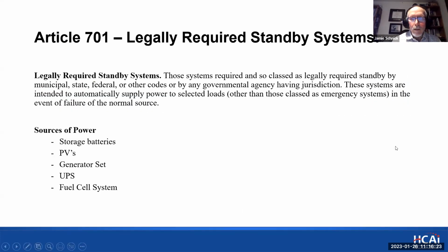Article 701. So the 701 legally required standby systems. The definition in the code is those systems required and so classed as legally required standby by municipal, state, federal, or other codes, or by any governmental agency having jurisdiction. They're intended to automatically supply power to selected loads other than those classed as emergency system in the event of failure of the normal source. So the code allows storage batteries, PVs, generator set, UPS, and fuel cell for sources for legally required standby systems.